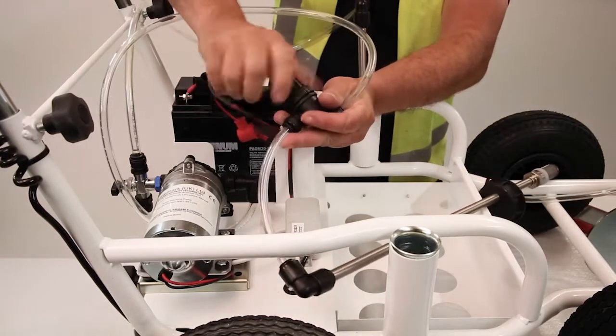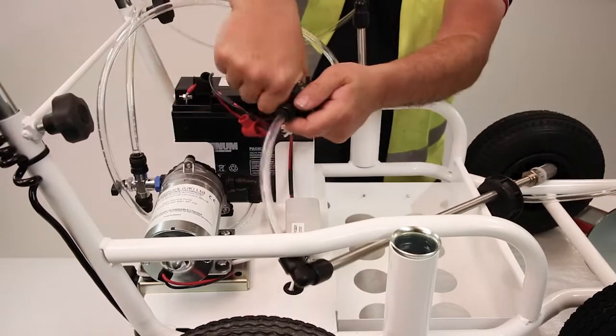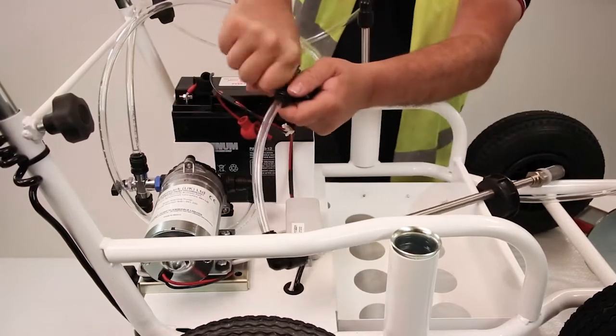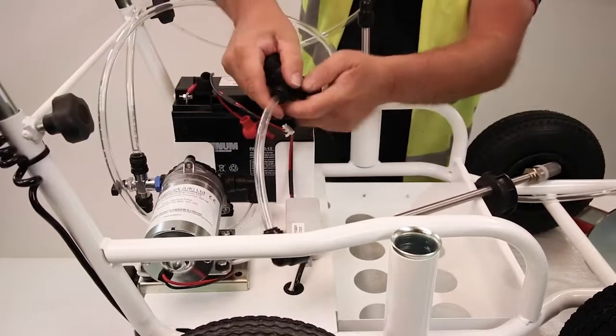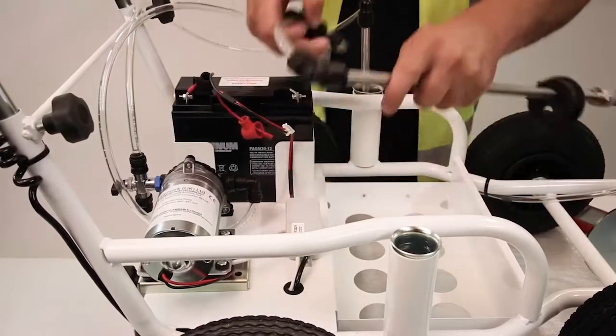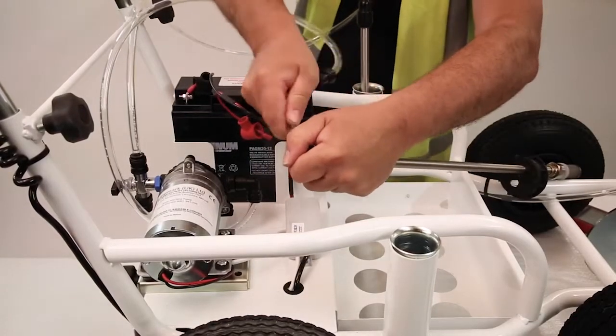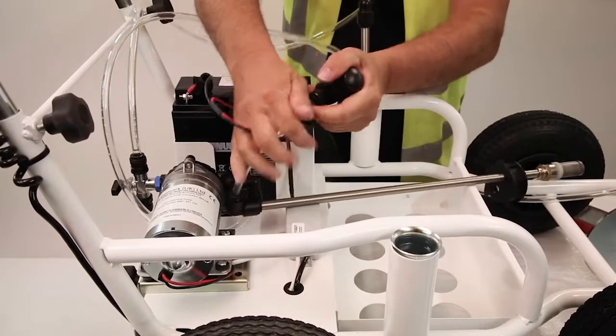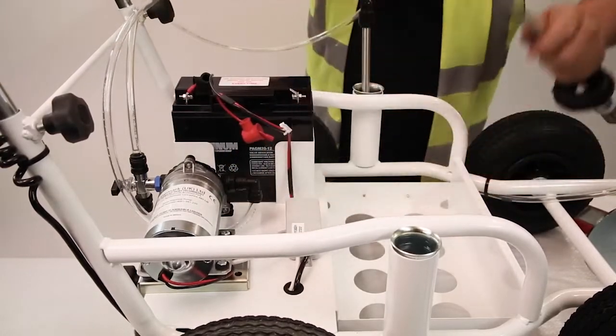When you close it back up, the most important thing is not to have any air getting into the system at all, because that will just lose your pressure and you'll see air bubbles being pulled in. That way you would always check that all the fittings are put fully in, so you're not drawing air into the machine.